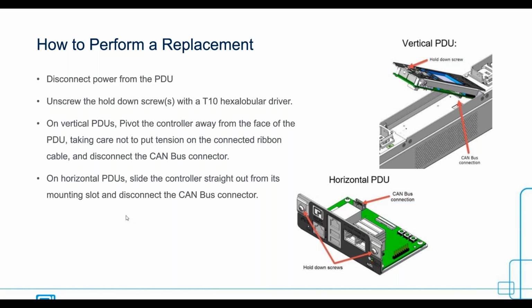The next thing you will do is unscrew the hold-down screws with the T10 driver. On vertical PDUs, removing the controller module will require pivoting the controller away from the PDU, meaning it needs to be lifted on the end that has the screw. Also, make sure not to create tension where the ribbon cable is connected, and then you can safely disconnect the CAN bus connector. On a horizontal PDU, it will be simpler since there are two screws and the controller can be gently slid out from the PDU chassis. After that, you can proceed to disconnect the CAN bus connector. When the CAN bus connector is removed, it's safe to completely remove the controller module.